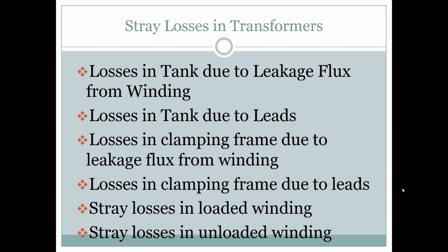Now, stray losses of a transformer happen because of this: losses in the tank due to leakage fluxes from the winding. Whatever flux is not connecting the secondary winding passes through, completing some circuit, either through the tank or whatever path is nearest. Then you have losses in the tank due to leads. After making the windings, we connect the leads to a terminal box. Those leads also carry flux and create losses. Then there are losses in the clamping frame, where we clamp with nuts and bolts; these complete the circuit of leakage fluxes and create losses.